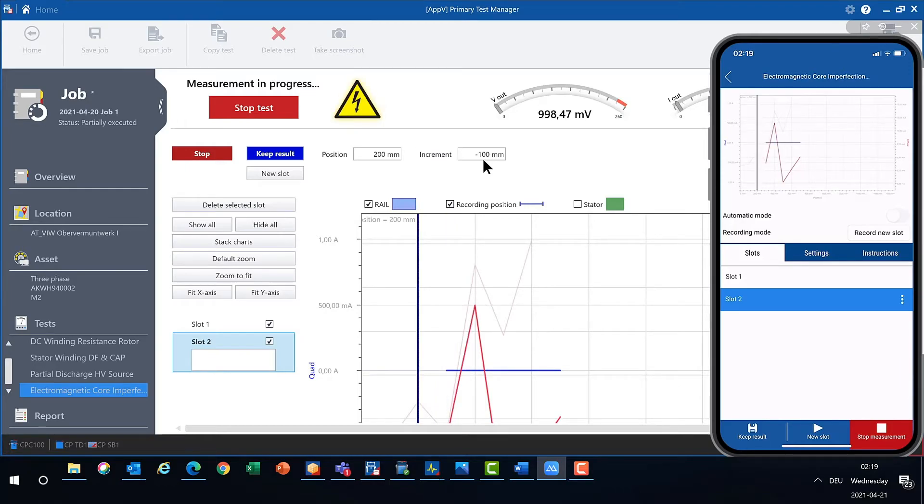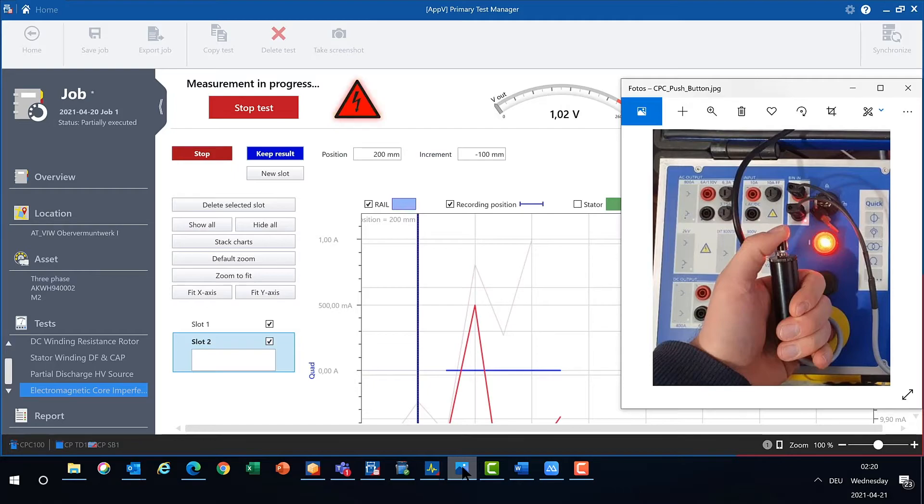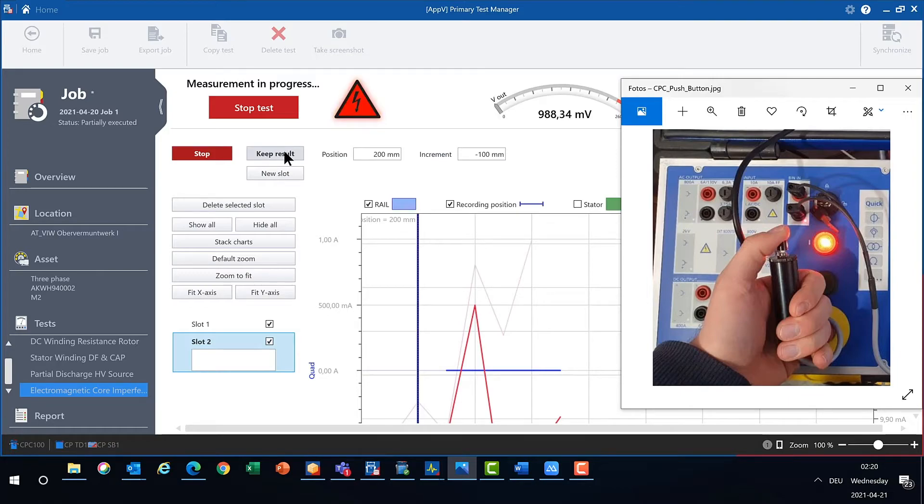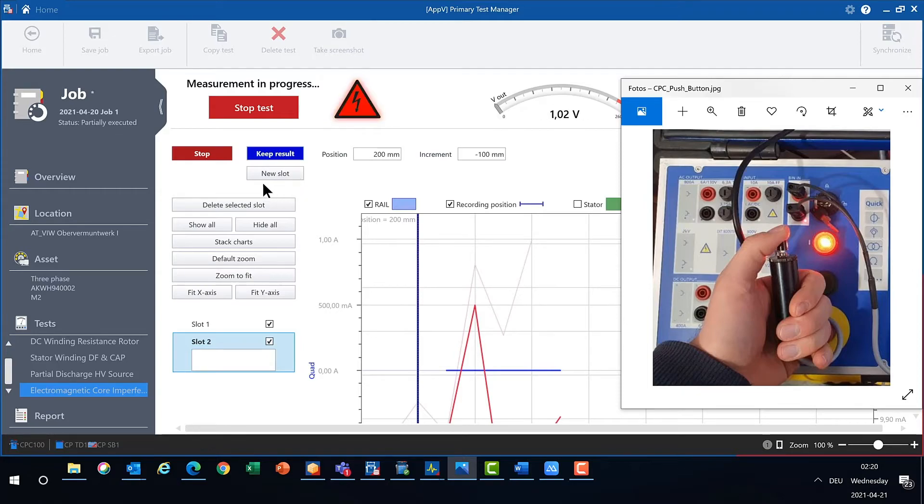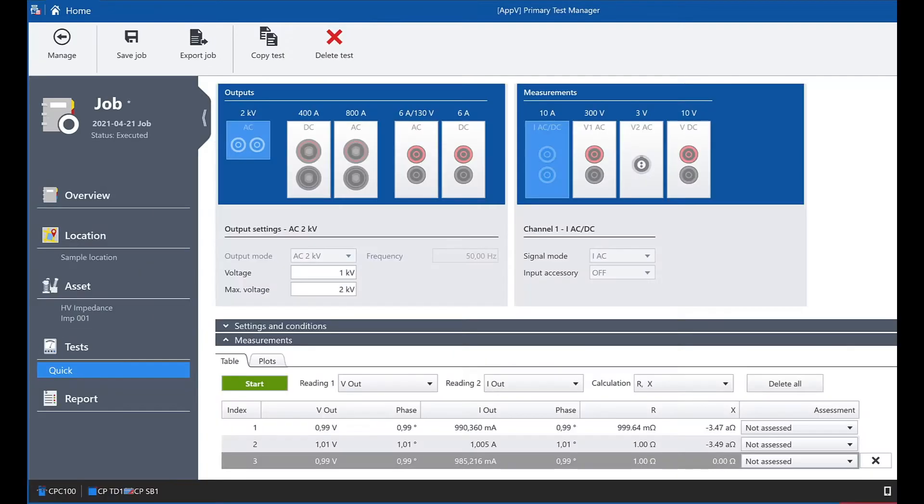If you don't have a smartphone in use and don't use PTMate, there is an alternative method. You can do the remote control by connecting a push button to the binary input of the CPC. Pressing the button for a short time will keep the result of a measurement. Pressing it for longer than two seconds will initiate the measurement of a new slot.